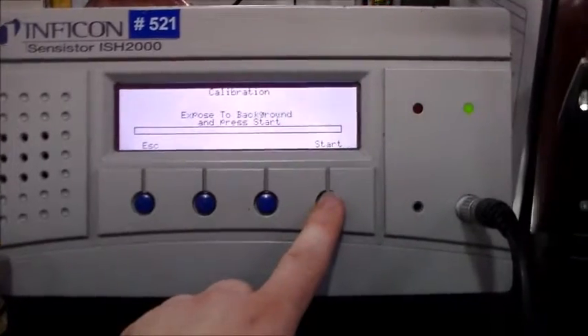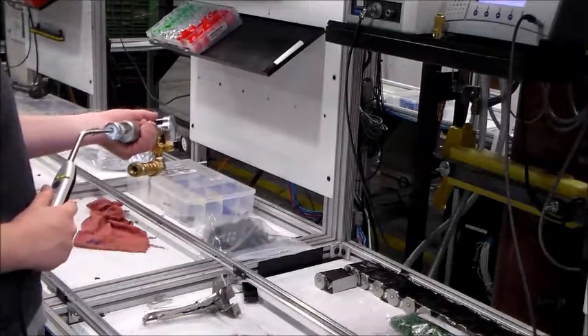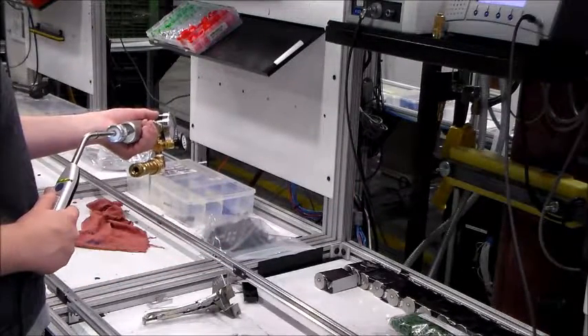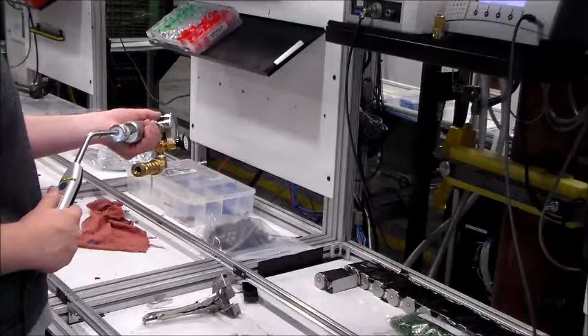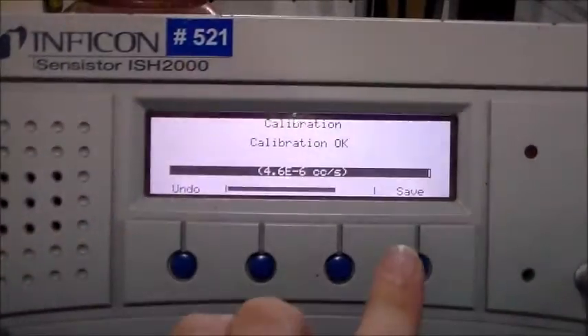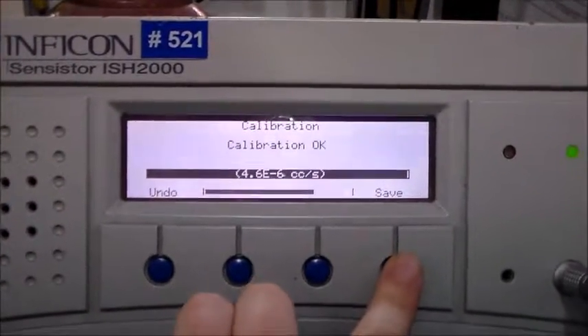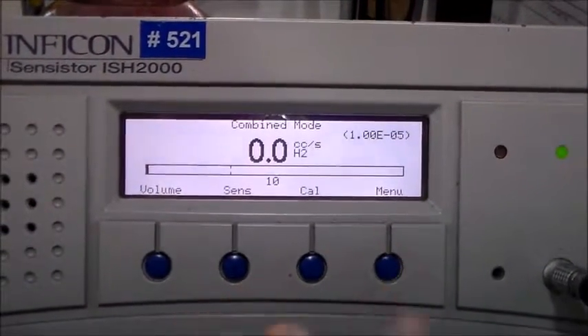Start the calibration by pressing the calibration button on the menu. Then press Start, then Enter. Follow the prompts on the screen, exposing the probe to the spot in the reference leak instrument until the calibration is complete. You may have to repeat this process a couple of times before pressing Save to complete the calibration once the Calibration OK message appears on the screen.